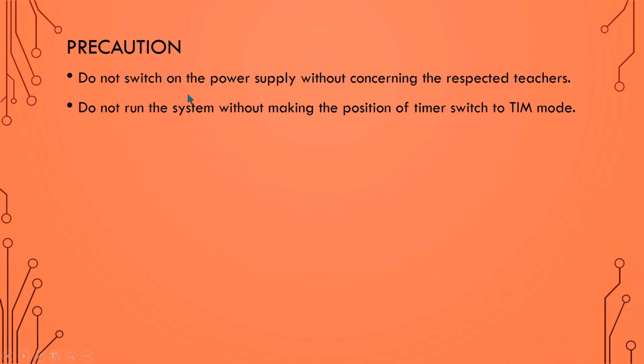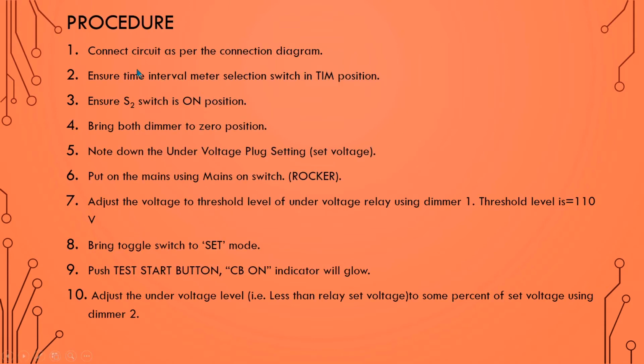So these are the precautions that we have to take. The technical precaution is: do not run the system without putting the timer switch in TIM mode. That means if you run without the timer switch in TIM mode, we cannot measure the operating time using the time interval meter. So now you will see the procedure one by one.